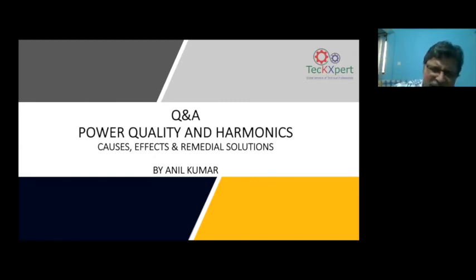Harmonics by itself cannot cause a problem just like that. Harmonics can be a problem, as I said, if the grounding is not okay, then sometimes through the grounding effect it can happen. But then quality has to be measured at the input of the UPS. If it is a regular problem, it's easy. Otherwise, you need a little longer duration measurement. And then we can solve this problem, I can tell you. Okay, so a study has to be recommended, right? Yeah, because you need to look at the voltage quality. You look at the harmonics, but you should also see the voltage quality.